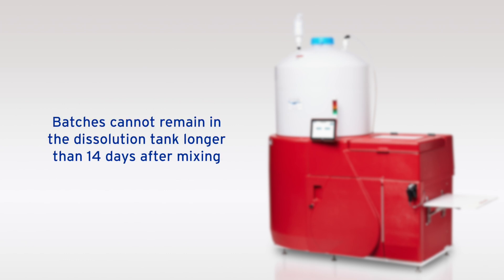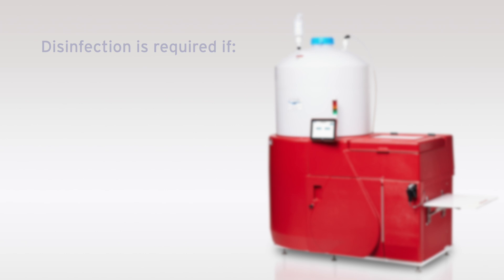Acumix will not allow any batch mixed more than 14 days ago to be transferred to a storage tank and will require the batch to be discarded. Do not allow batches to remain in the dissolution tank longer than 14 days after mixing. Prior to mixing a batch of acid, determine whether or not disinfection is required.